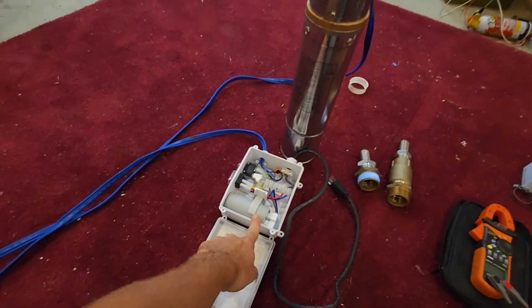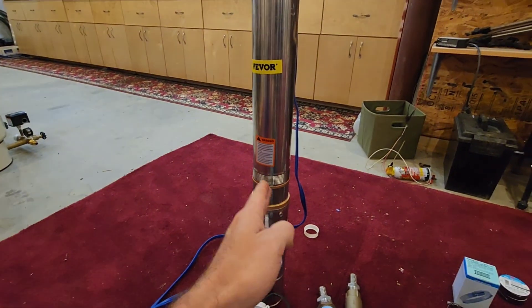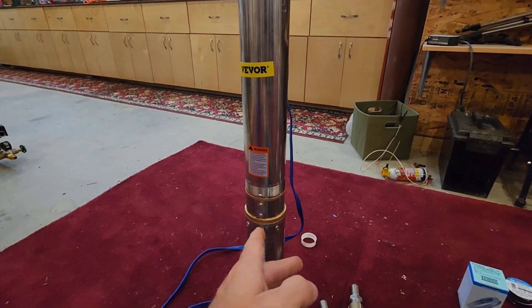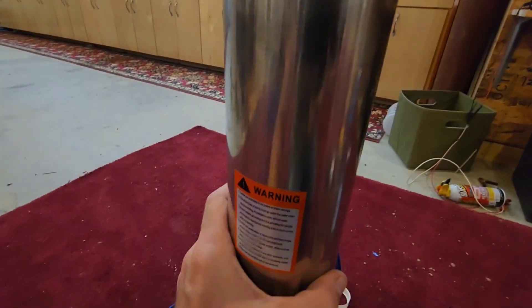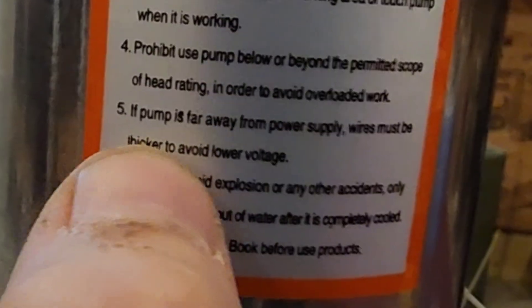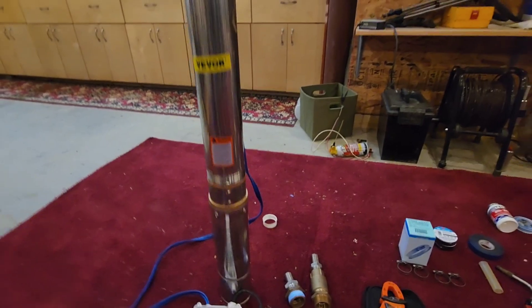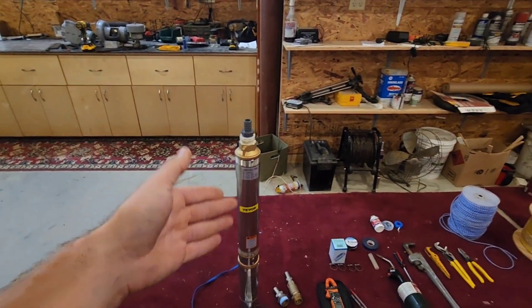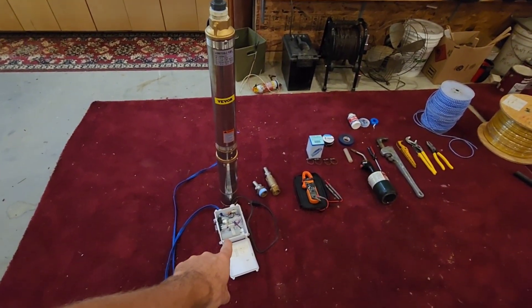The wire that comes with the VEVOR well pump is 16-3 wire, and it goes into the control box. If you choose to put this pump past 130 feet, you're going to have to change the wire. The warning reads: if the pump is far away from the power supply, wires must be thicker to avoid low voltage. That is very important because as voltage drops, amperage goes up, the pump has a harder time running, the wire can get hot, and then the control box will actually burn out.